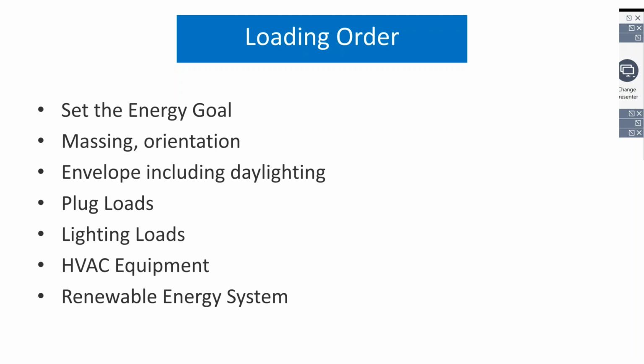Now, what's interesting - and we could have an entire webinar just on plug loads - a lot of times it means how effectively those plug loads turn off when the building is not occupied. I heard a story recently that a high school had 215 Wi-Fi routers in it, each using around 10-plus watts. Suddenly that's 2 to 3 kilowatts just in Wi-Fi, running 24 hours a day. Being able to get that equipment turned off can make a big difference in the energy consumption of the building when it's not occupied and nobody's using the Wi-Fi.